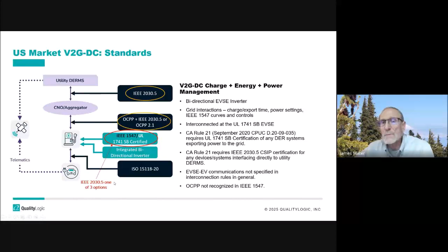But it's just been released, and it's not mature like IEEE 2030.5 is. On the inverter itself, there's a requirement to meet the interoperability requirements of 1547, and IEEE 2030.5 is one of those, along with SunSpec Modbus and DNP3.